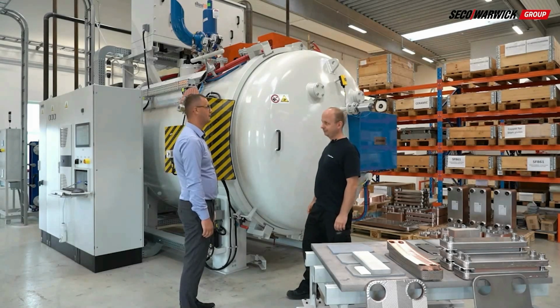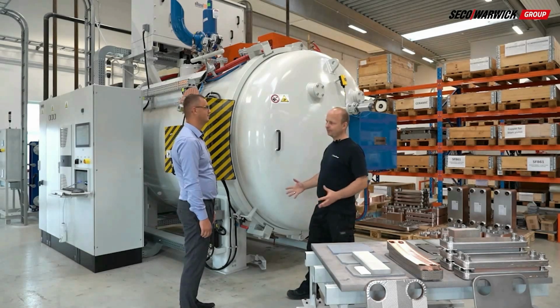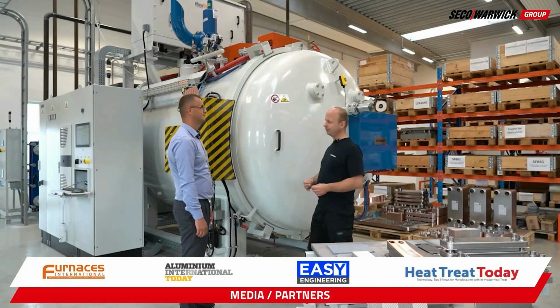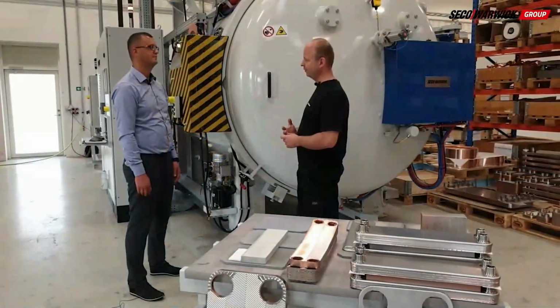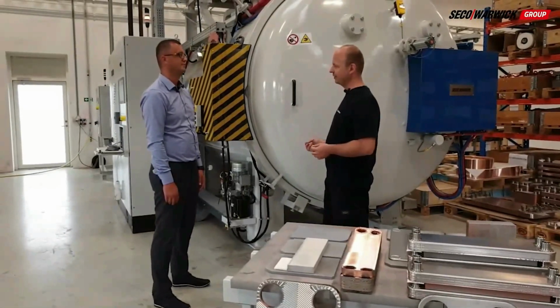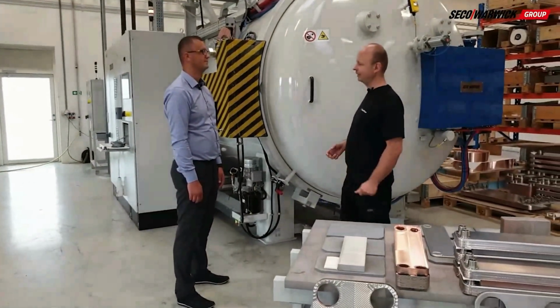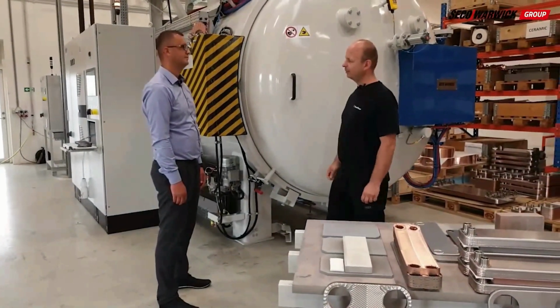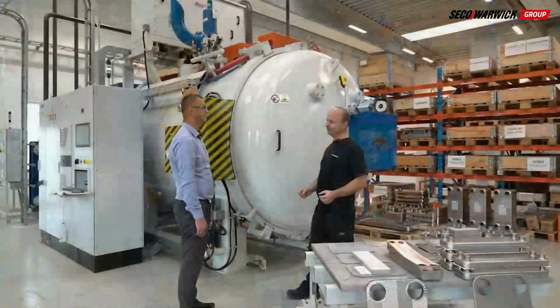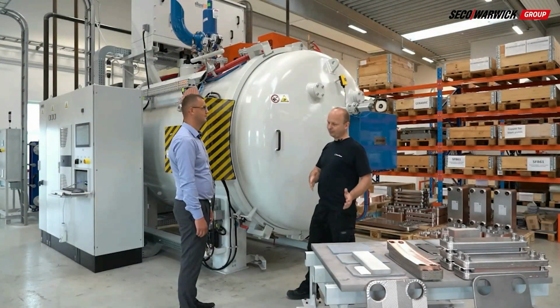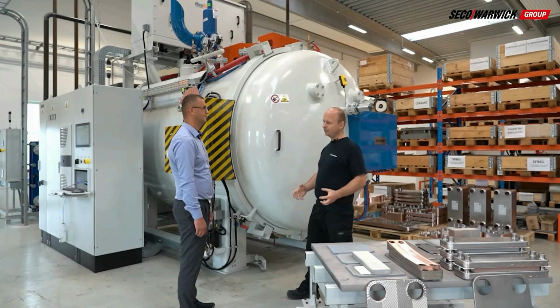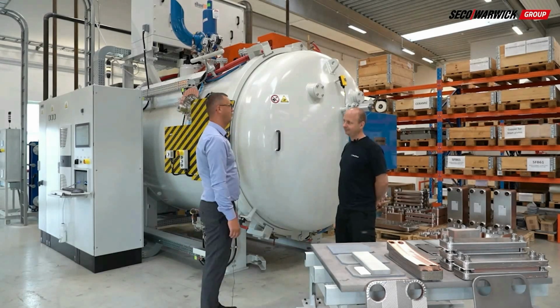What is most critical during the brazing process? It's very difficult to say what is the single most critical point—there are many critical points. From the beginning, when you cut material, you have to take care of the right dimensions. When you press the plates, you have to take care of the tolerances. When you're brazing, the tolerances of every parameter are really important, like temperature and vacuum range. I cannot tell you exactly which parameter is most important, because if you fail with only one of the processes, the final brazing result is not okay. So in every step you have to take care of the tolerance ranges, which are critical.